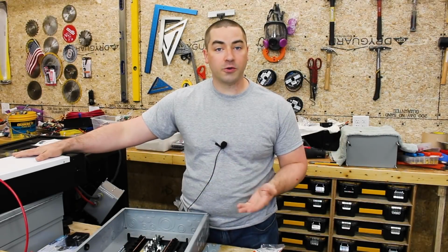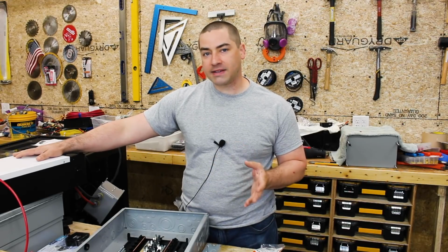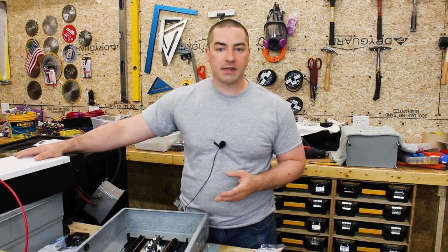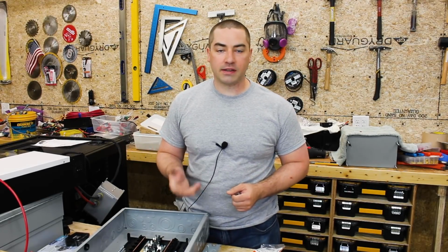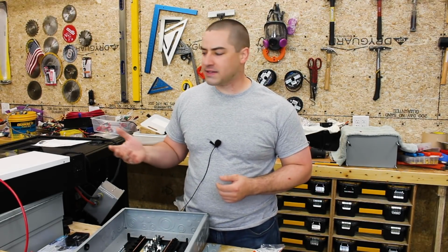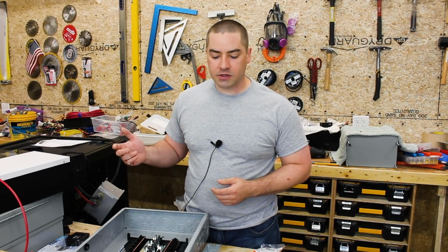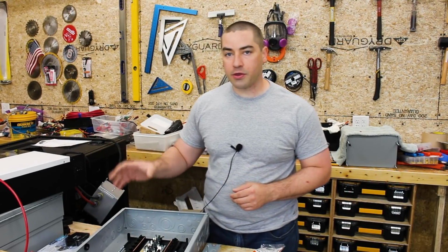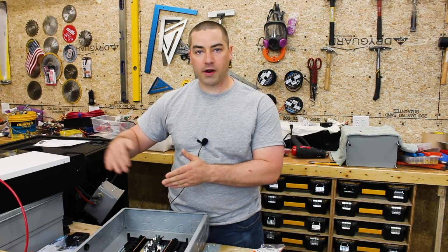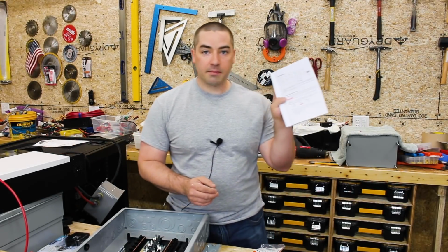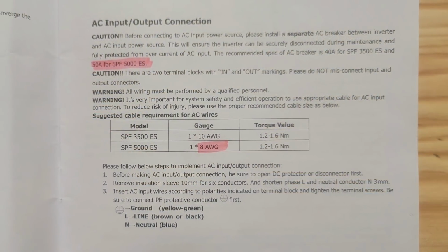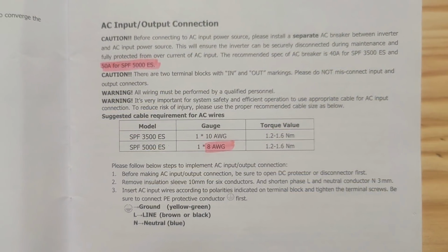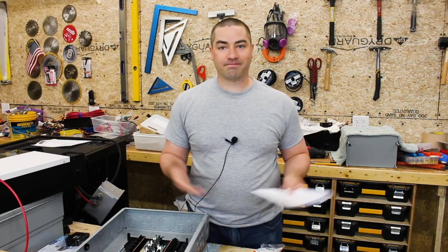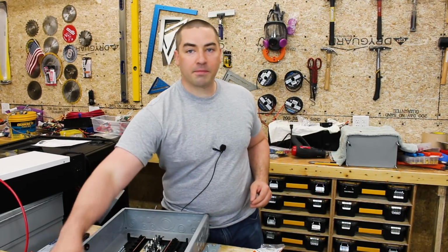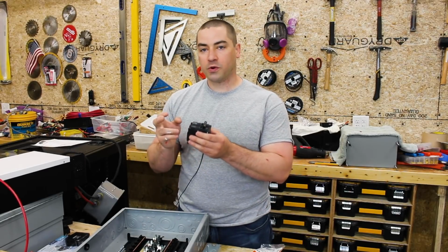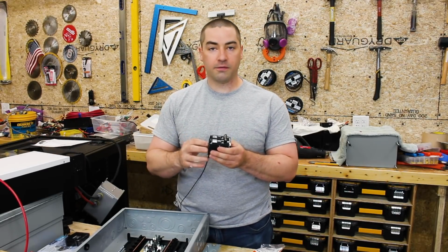This inverter is putting out 240 volts, which means it maxed out, it's just under 21 amps. Now, even if I factor in the 25% continuous duty requirement, that's still, I think, 26 amps. So I was originally planning on just using 30 amp circuit breakers with 10 gauge wire connecting the two. However, in the manual on page 9, it says 50 amp breaker with at least 8 gauge wire. So I did go out and pick up a 50 amp circuit breaker, which we're going to be backfeeding from the Growatt into the 50 amp circuit breaker.